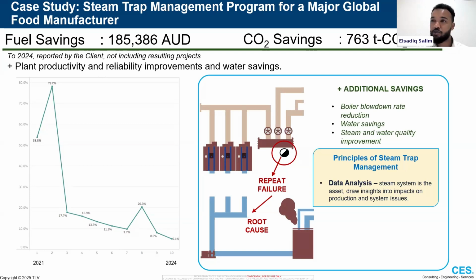The next slide will talk about the costs associated with that, but I wanted to highlight that these are surveys between 2021 and 2024. They've had 10 surveys, meaning they've looked at their production schedule and worked with their inspection company to make sure every steam trap is able to be tested, following that trend of getting the failure rate down below 10%.